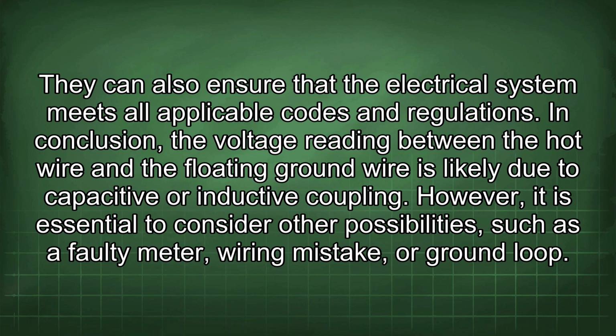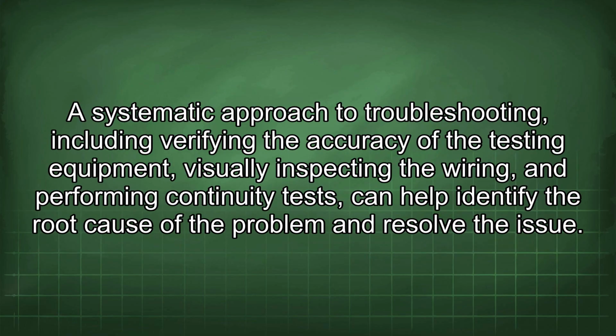In conclusion, the voltage reading between the hot wire and the floating ground wire is likely due to capacitive or inductive coupling. However, it is essential to consider other possibilities such as a faulty meter, wiring mistake, or ground loop. A systematic approach to troubleshooting, including verifying the accuracy of the testing equipment, visually inspecting the wiring, and performing continuity tests, can help identify the root cause of the problem and resolve the issue.